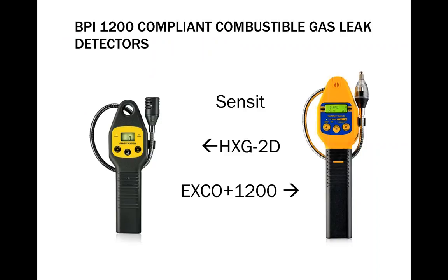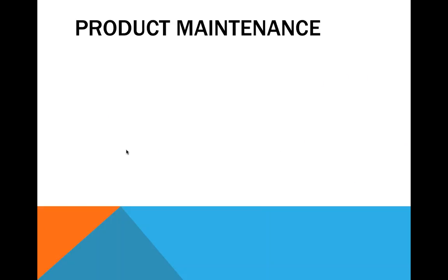We do have a couple of BPI 1200 compliant combustible gas leak detectors we sell. The one on the left, the HXG2D by SENSIT, is made in Valparaiso, Indiana. Great people, great factory. I've worked with them for years. They developed that device specifically for an industrial situation, but it overlays very directly onto the BPI 1200 spec. That's available for less than $400. The one on the right, the EXCO Plus 1200, covers the OSHA and the BPI 1200 requirements together, and we'll talk about that in a moment. That's really the first dedicated monitor covering both of those factors. It does the gas leak detection with the 10% LEL.